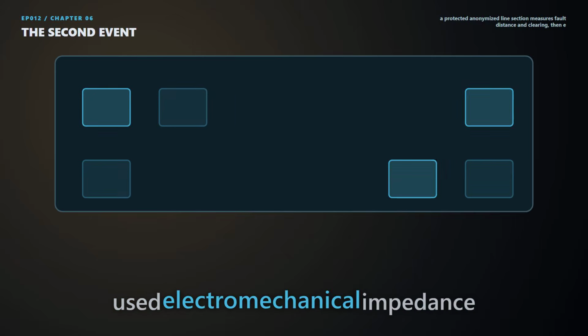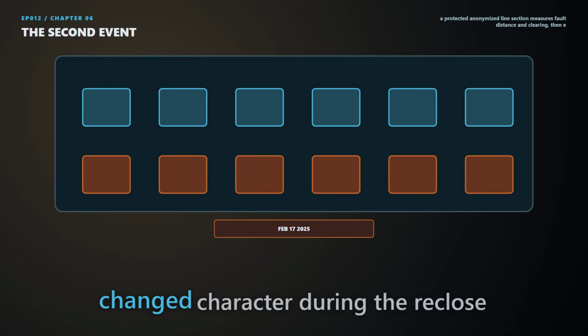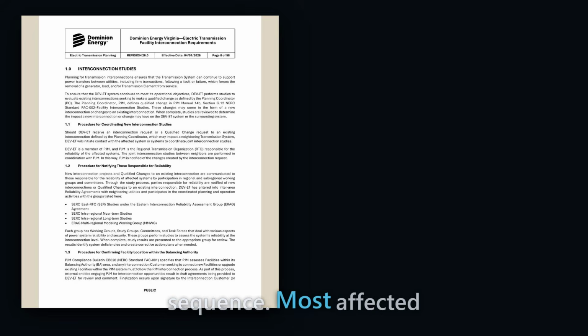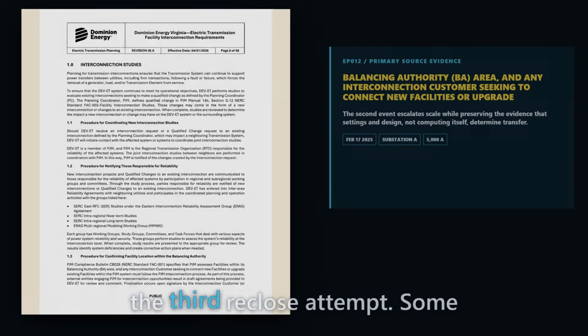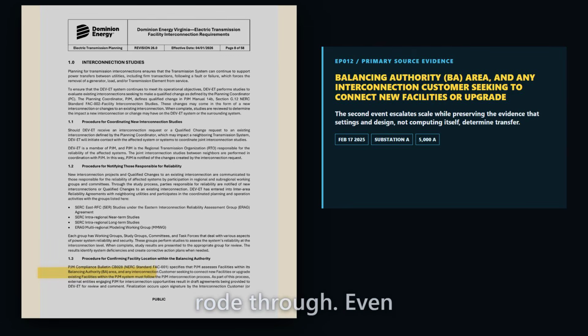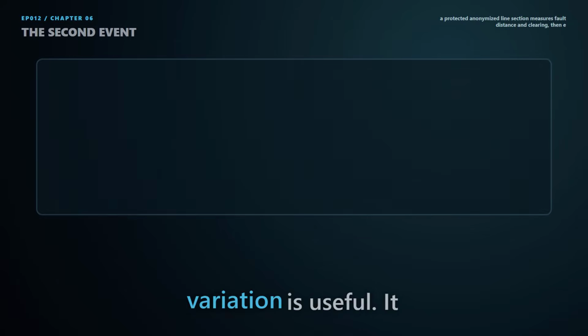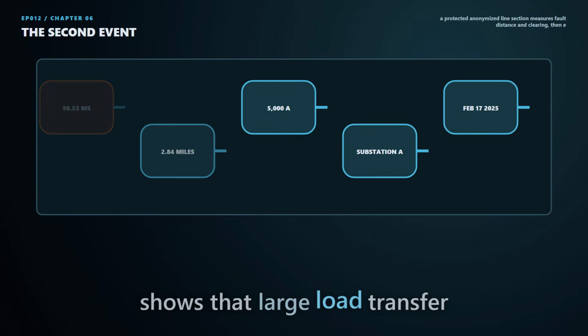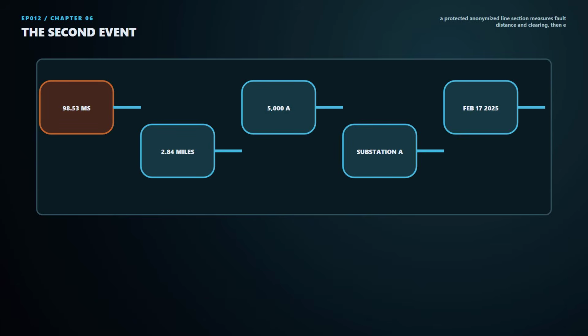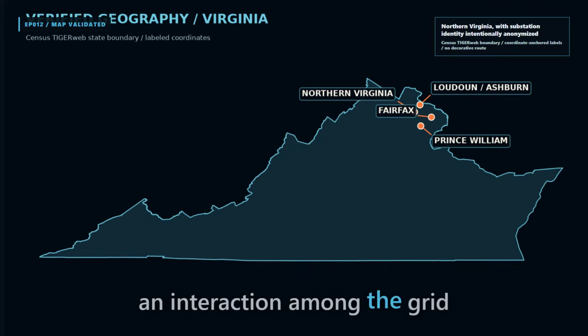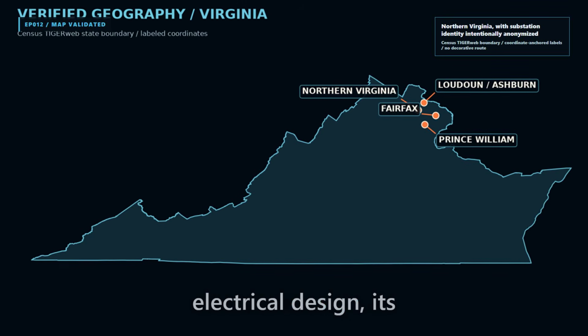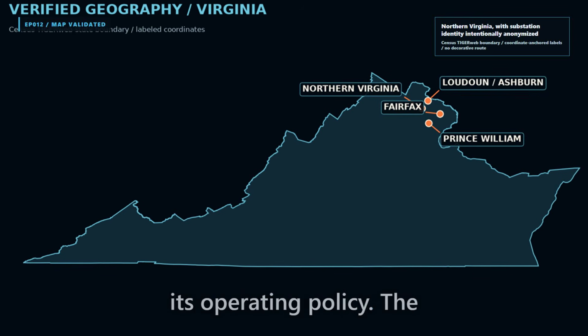The line used electromechanical impedance relaying, and the fault changed character during the reclose sequence. Most affected data centers transferred after the third reclose attempt. Some rode through. Even facilities belonging to the same customer did not always respond in the same way. That variation is useful. It shows that large load transfer is not an unavoidable property of computing. It is an interaction among the grid waveform, the facility's electrical design, its protection settings, and its operating policy.